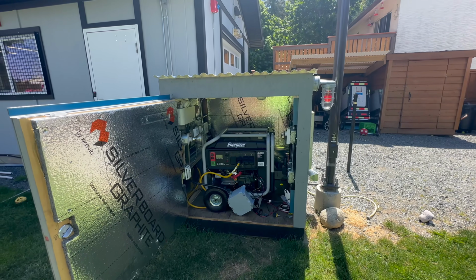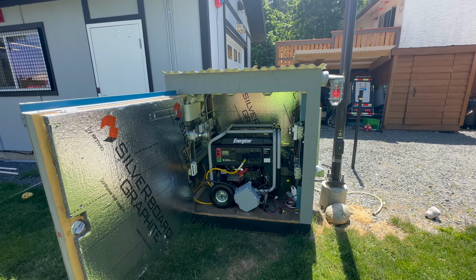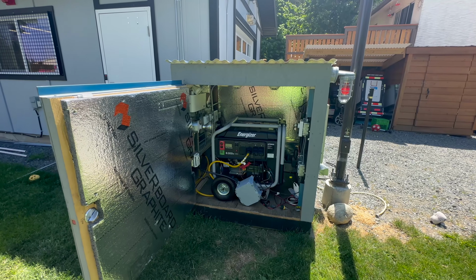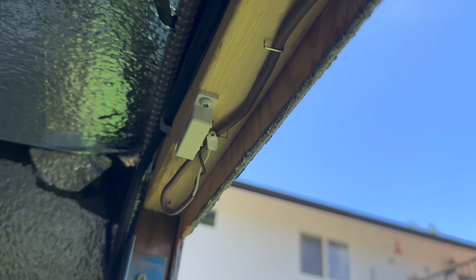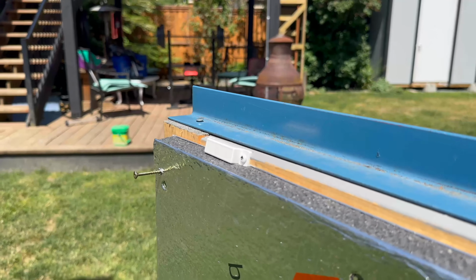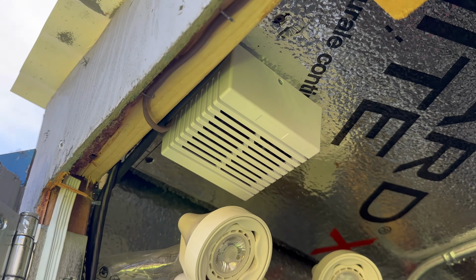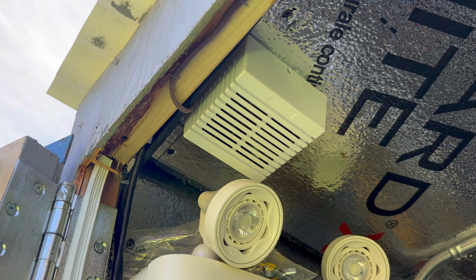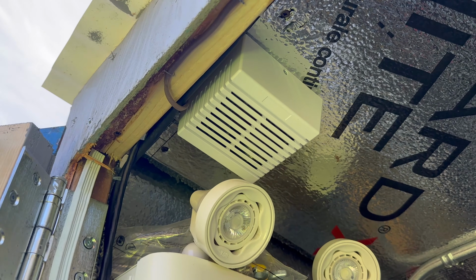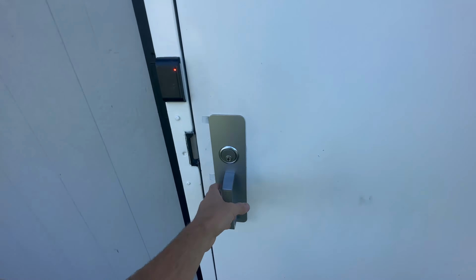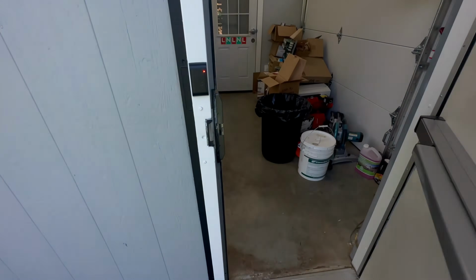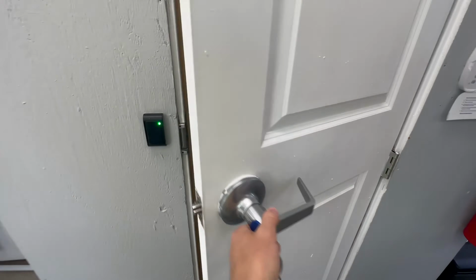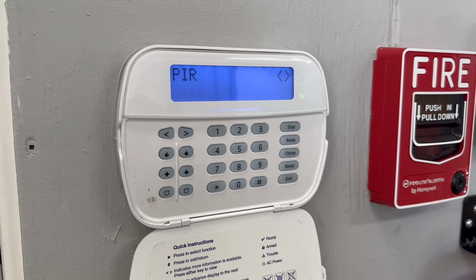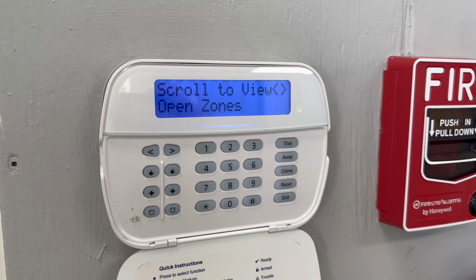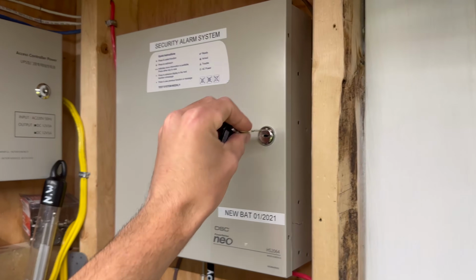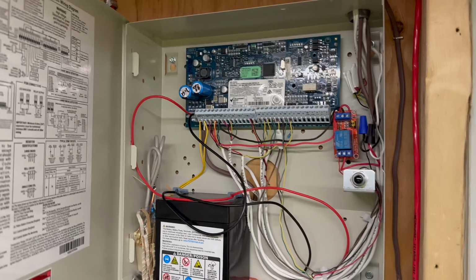Last thing before we get into the generator itself is we do have intrusion alarm, part of the security system in this building. There is a door contact on the door, which will read the door magnet on the door itself, as well as an external siren to add to the overall siren volume, as there is another siren mounted inside the main building. Those all connect back to the main security panel, where we have our security keypad right here, and it will scroll through to say generator room, showing what zones are open, which those tie in to the security panel right here.